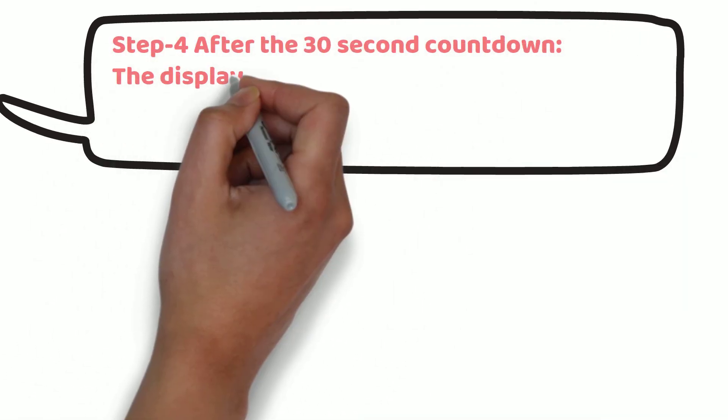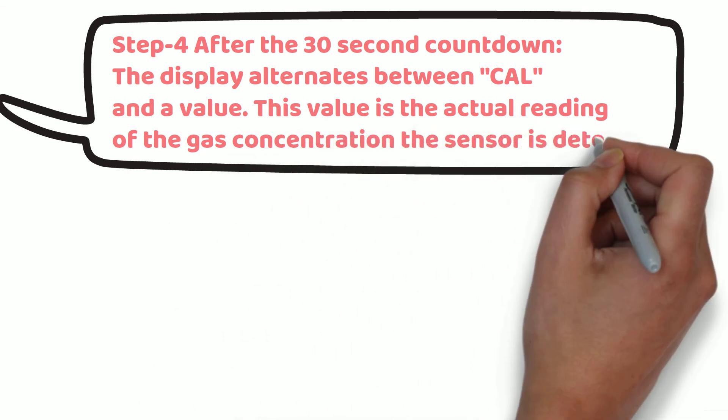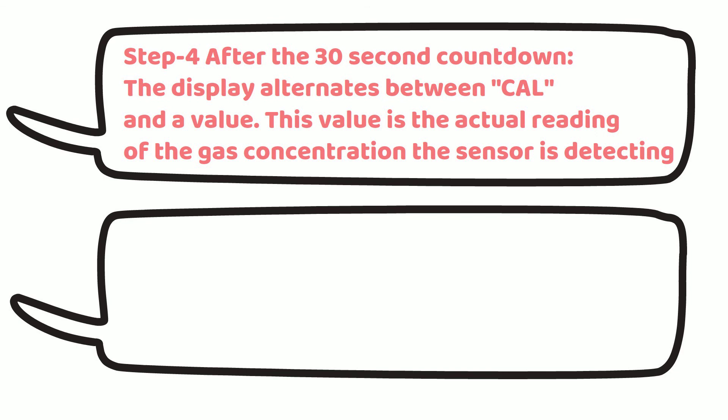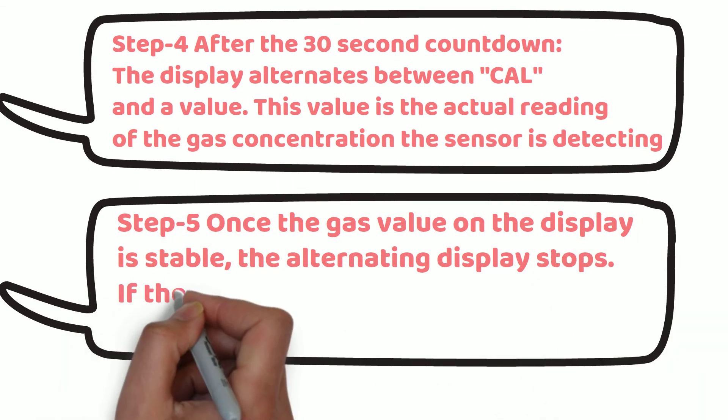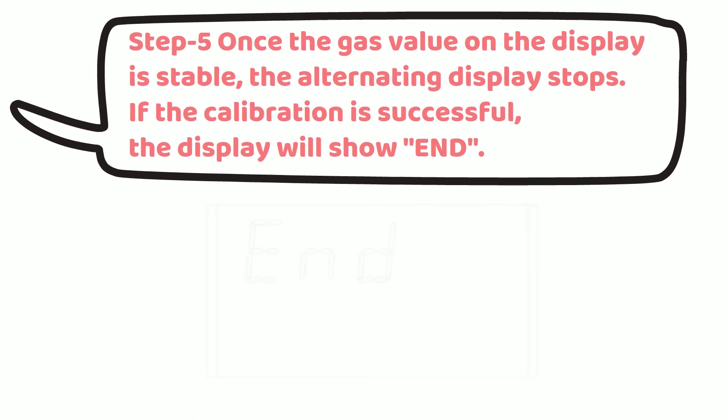After the 30 seconds countdown, the display alternates between cal and a value. This value is the actual reading of the gas concentration which the sensor is detecting. Once the gas value on the display is stable, the alternating display stops. If the calibration is successful, the display will show end. End on display indicates that zero calibration is successful.